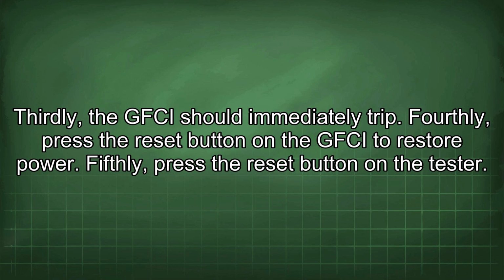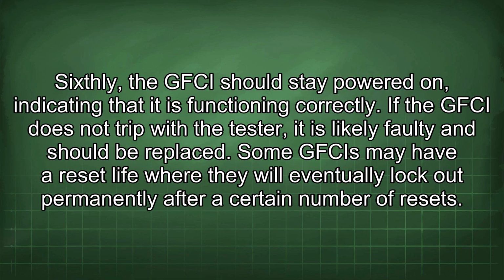Fourthly, press the reset button on the GFCI to restore power. Fifthly, press the reset button on the tester. Sixthly, the GFCI should stay powered on, indicating that it is functioning correctly. If the GFCI does not trip with the tester, it is likely faulty and should be replaced. Some GFCIs may have a reset life where they will eventually lock out permanently after a certain number of resets.